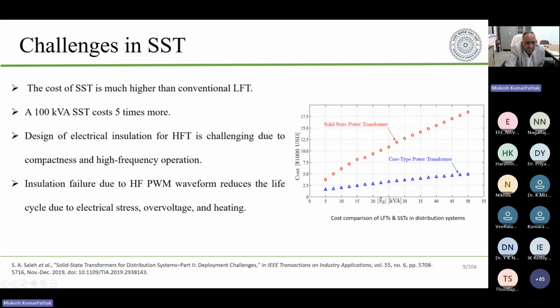Then the other thing is that design of electrical insulation for high frequency transformer is challenging due to compactness and high frequency operation. So the transformer, you make it compact. When you are making it compact, the area available for cooling and heat dissipation is also reducing. So that creates more challenges.